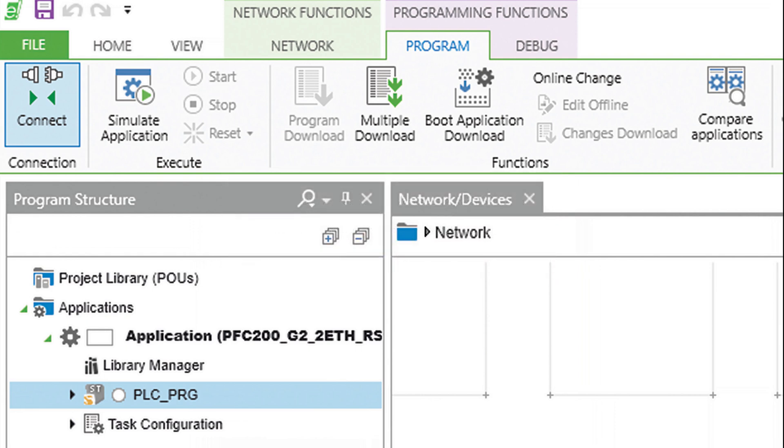Downloading in this method means that the project is only being placed in RAM memory. The controller will run this project after clicking the start button, but upon power cycle it will resort to the previous running project.